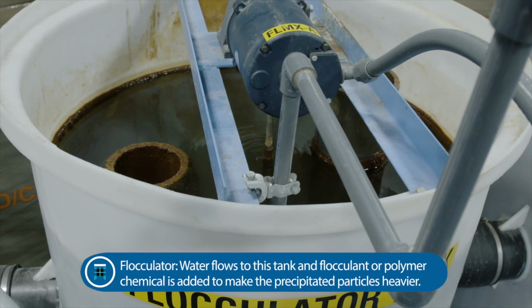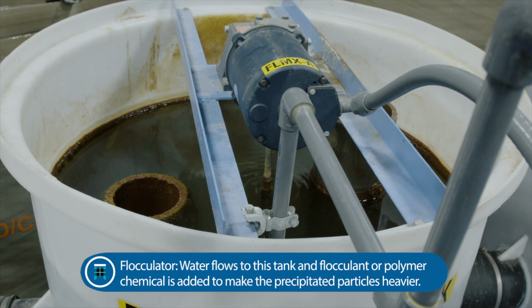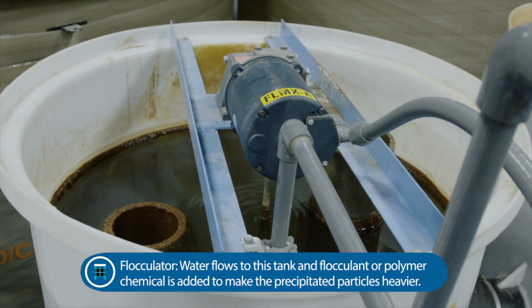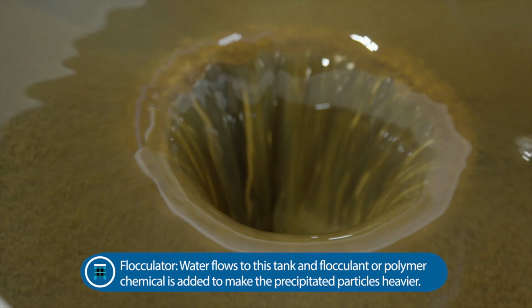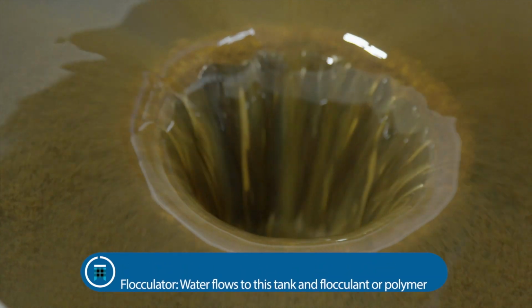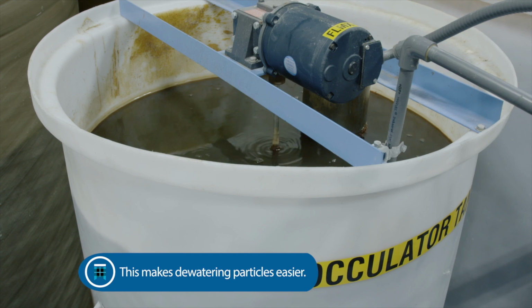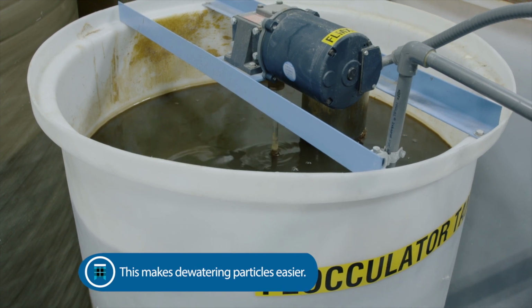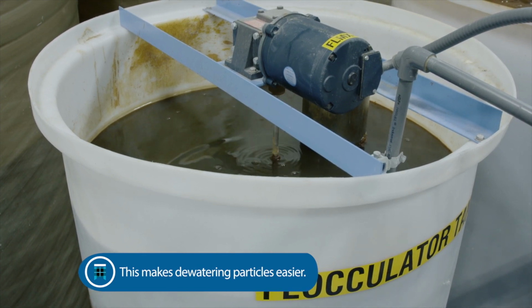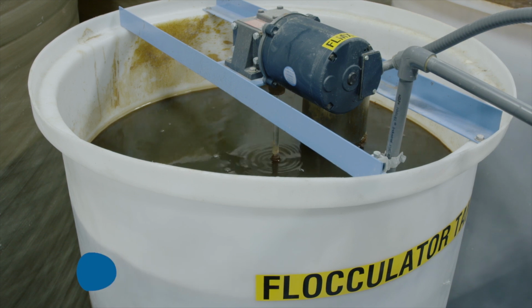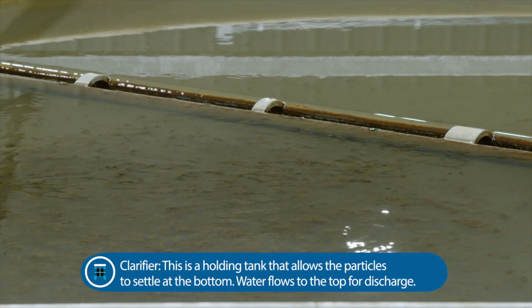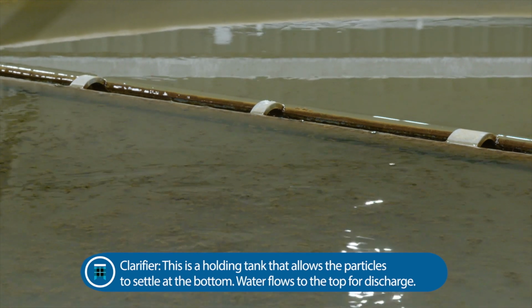Water flows to a flocculation step where polymers are added to accelerate precipitation of heavier particles. This improves dewatering efficiency. A bulk holding tank allows the particles to settle and clean water to flow to final discharge.